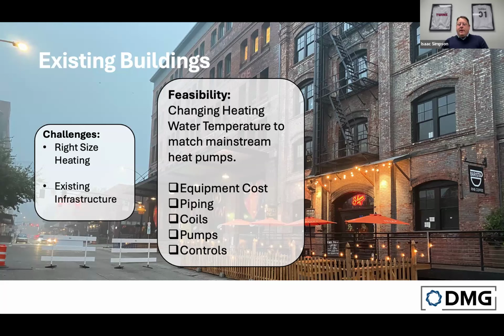Maybe that could be 170 or 165. Then, if we can figure that out, how much of the existing system can we reuse? On several projects we've looked at, when we considered 120 or 130 degree water from a conventional heat pump, the equipment cost wasn't the problem. It was repiping the building, changing all the coils, the massive labor, and tearing out the guts of the building and replacing them that became the limiting factor.